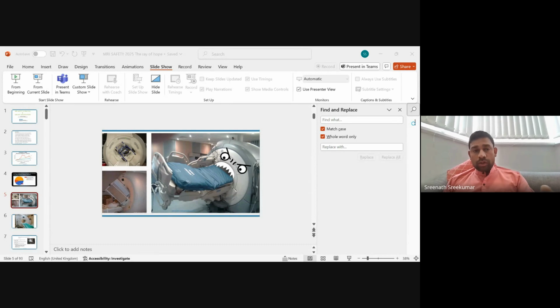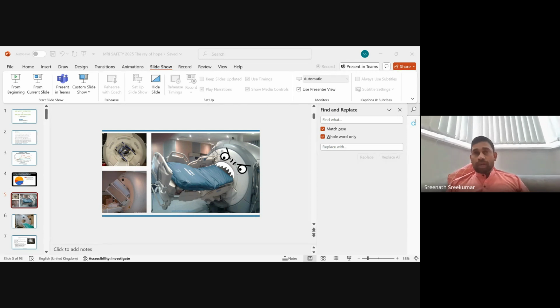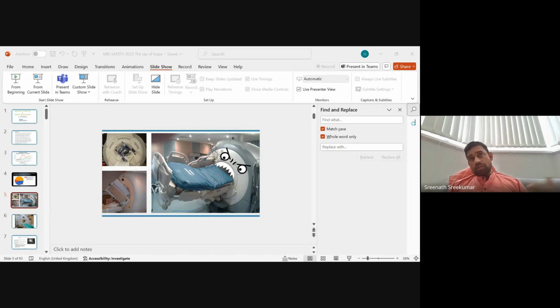Some of the incidents involve a trolley or bed and other hospital-related equipment, and this is an oxygen cylinder. Oxygen cylinders are not allowed inside the scanner rooms, so everybody needs to be aware of it. Maybe sometimes we think about X-ray and CT. We can go into an X-ray or CT scanner room with an oxygen cylinder, but MRI is not acceptable with an oxygen cylinder. Another problem is that if personnel are injured inside, we have to go for a procedure called quenching, which is turning off the magnet for life-threatening emergency situations. Severe damage to the equipment will happen from quenching.